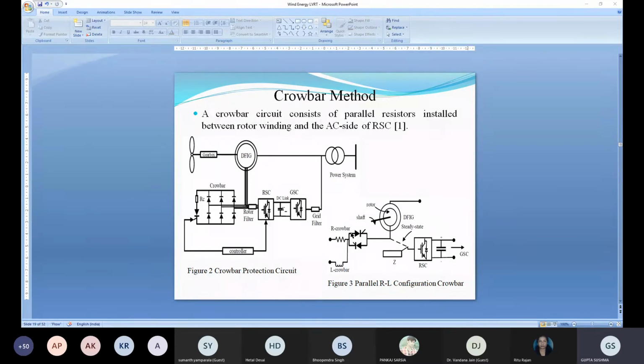Another configuration is the parallel R and L crowbar circuit, which is also connected between the rotor and RSC. That will control the overcurrent by consuming power and taking reactive power from the rotor side.